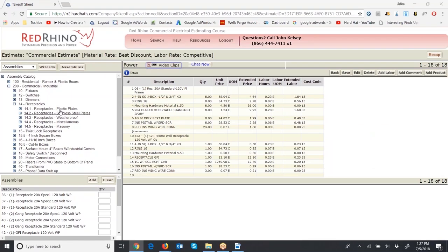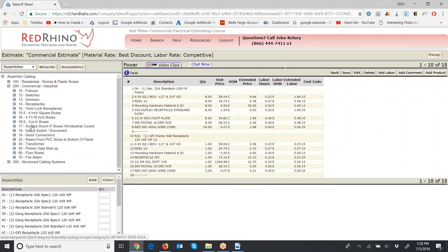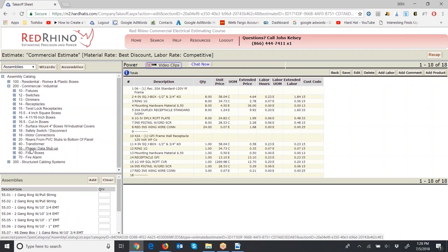Next on the list is a data stub-up — quantity of five. These assemblies are really slick. Assembly Catalog 200 is always commercial industrial. Category 55 is phone data stub-up. In the Assembly Catalog you can click the minus sign to collapse the menu, then go down to category 55 phone data stub-up. It doesn't have a plus sign next to it — no subcategories — so just click on it and it displays the assemblies. Notice it has options like a one-gang ring with pull string, a two-gang ring with pull string, a one-gang ring with 10 feet of 3/4-inch EMT, and so on.